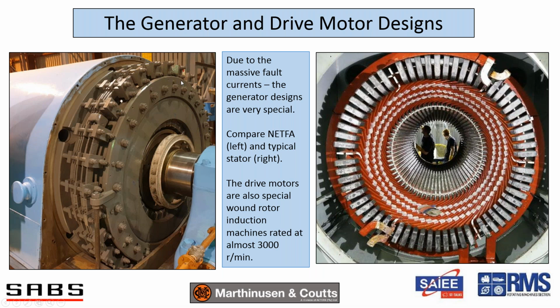What a designer might ask is, if it's totally encapsulated and covered, what happens to cooling? That introduces the next special aspect about these machines: they don't really need to cool that well from a continuous point of view, because they are only subjected to very short-term currents. A typical test is a second or two. So they don't have to have continuous cooling. That applies to the rotor as well as the rest of the stator where the coils are fitted in the slots.